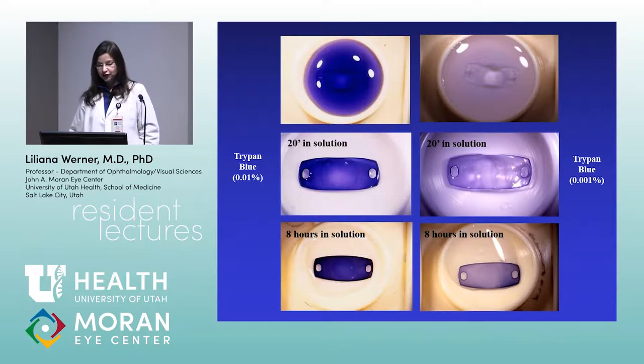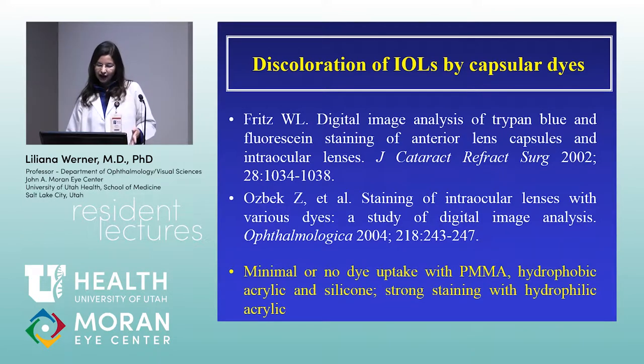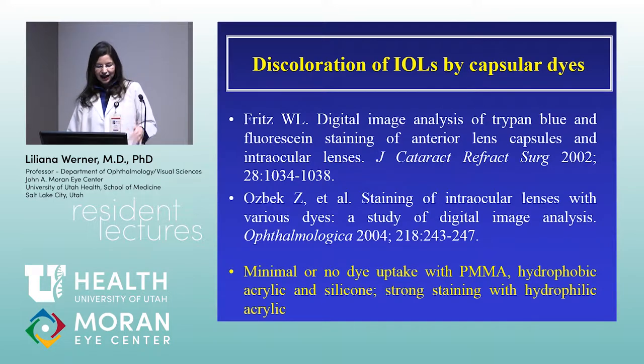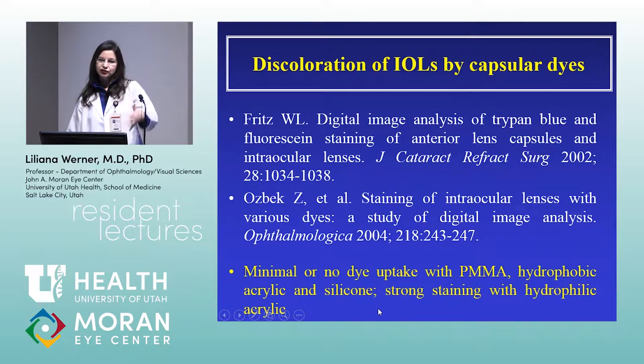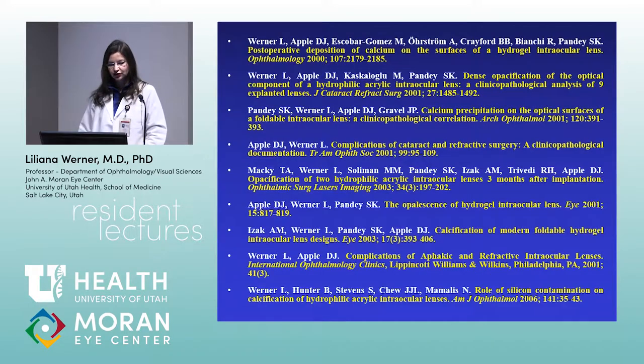Testing revealed that even diluted residual trypan blue remaining inside the capsular bag can be absorbed by the lens as it expands. There is no way to remove the dye once absorbed. After this complication, many studies evaluated the interaction of all IOL materials with different capsular dyes. The conclusion was that it doesn't happen frequently, but hydrophilic acrylic lenses not fully hydrated at time of insertion are at risk. If the lens is fully hydrated before placement, discoloration should not occur.